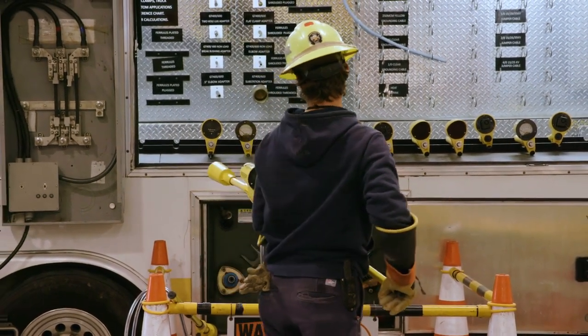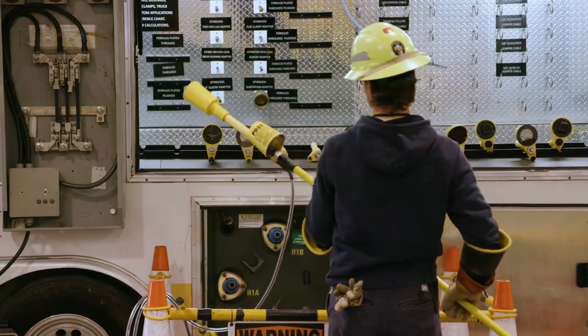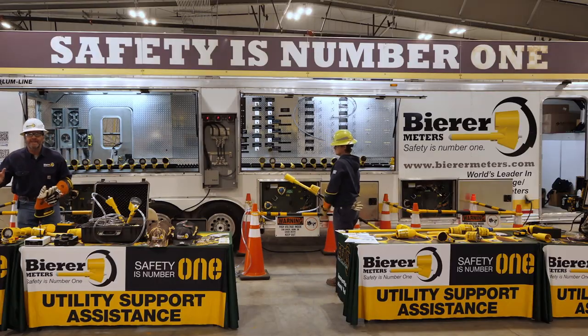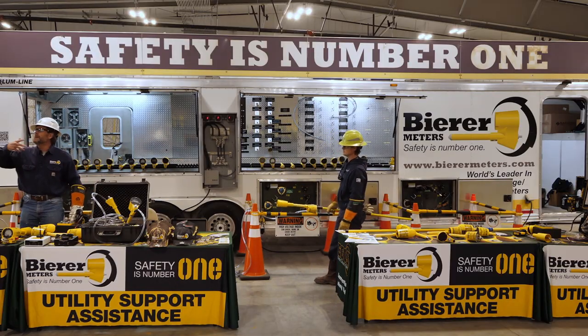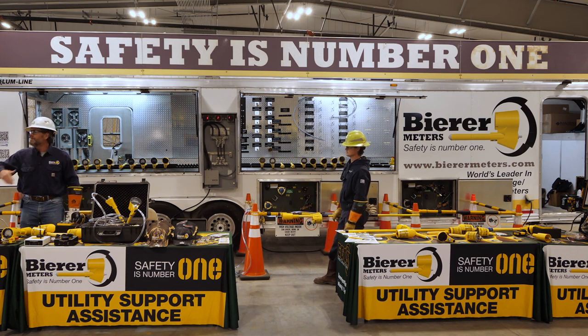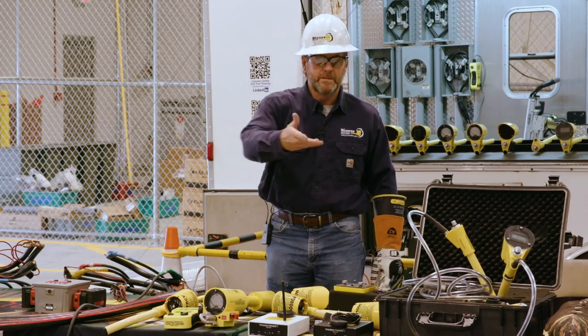Zero. Okay, zero. The reason why you want to always take the meter head off last is you want the meter to speak to you. When the meter speaks to you and you see zeros on that tool, then the meter is telling you that the tool is de-energized, okay?